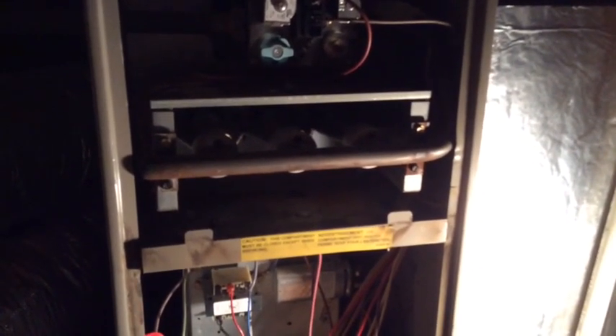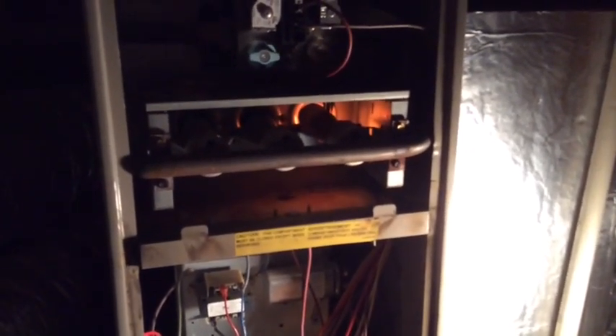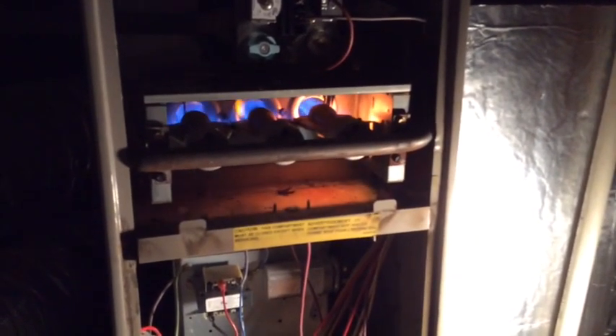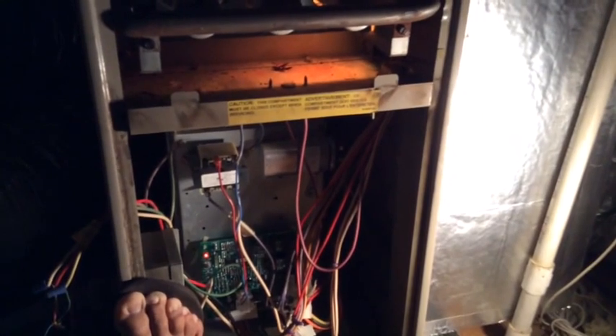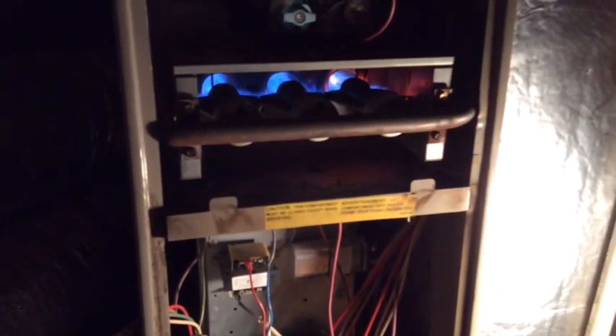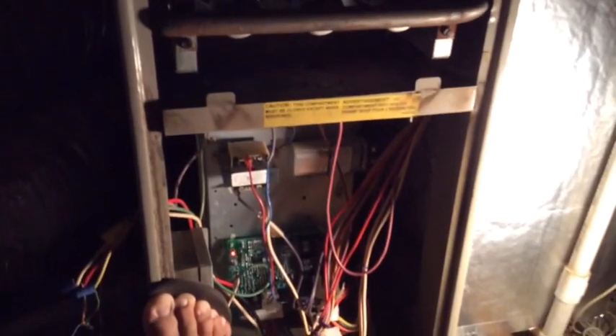So then the inducer's firing. It's received a call for heat from the unit downstairs, the thermostat. That was the sound of the relay, I believe, for the hot surface igniter. And there it goes. And then the relay for the heat for the gas valve, and it's going. And then that's the relay for the hot surface igniter going off. It looks like it was the control board.